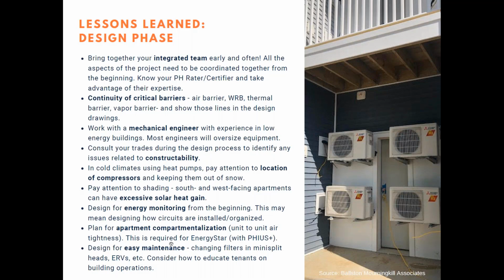And then the last piece on the design side is really thinking about the maintenance of this equipment. I've seen some pretty crazy installations for ERVs, like hidden in the top of a closet, where there's no way you can really get at it to open up the unit. Both the mini splits, ERVs and HRVs have filters that need to be changed on a regular basis, like once or twice a year.